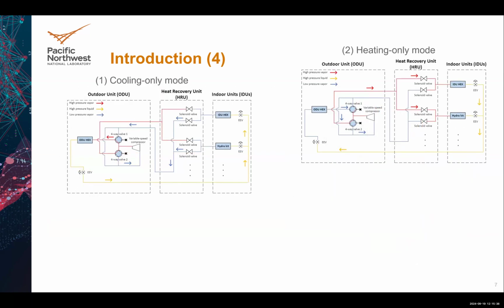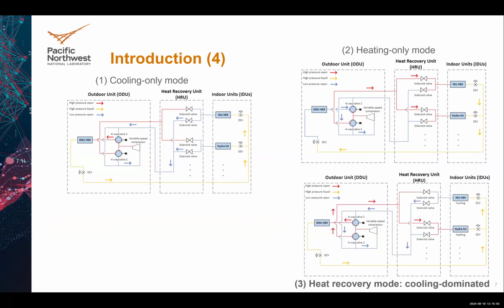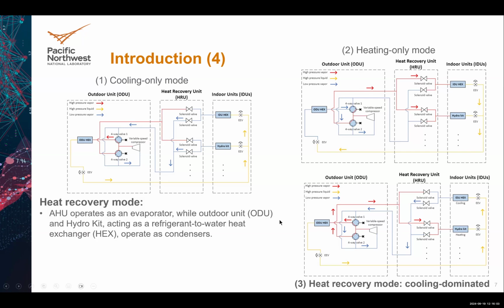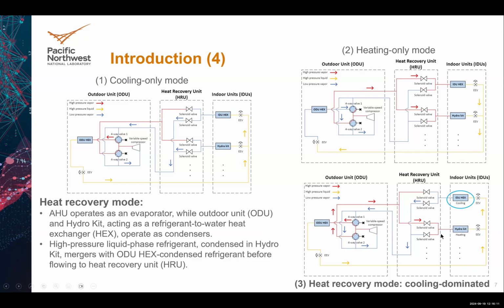Okay, we have briefly talked about the system, but it's very important that we know its operation algorithm, right? For a heat pump system, you can provide heating or cooling, right? That's the normal operation mode. However, for this unique MF-VRFHR system, we have what we call a heat recovery mode. In heat recovery mode, you have the heat recovery unit operated as the evaporator. You have the outdoor unit and the hydro kit serve as the condenser.